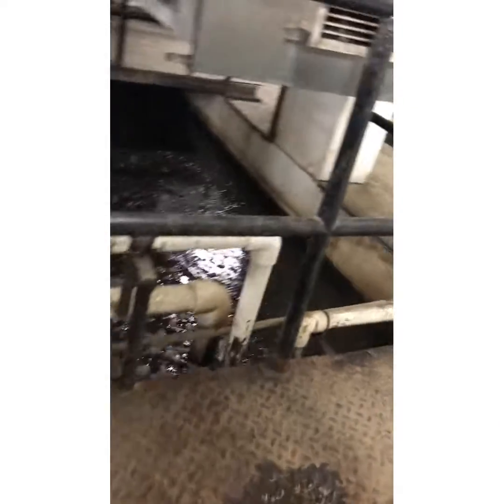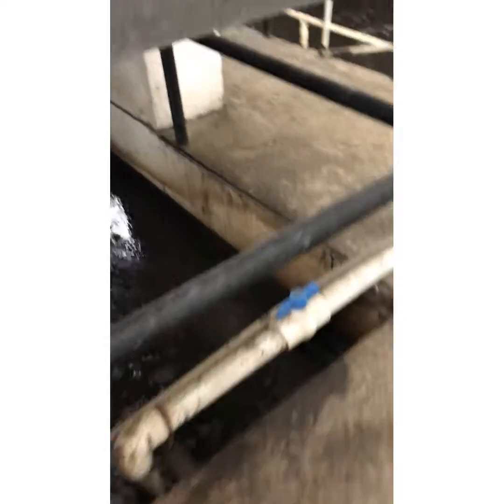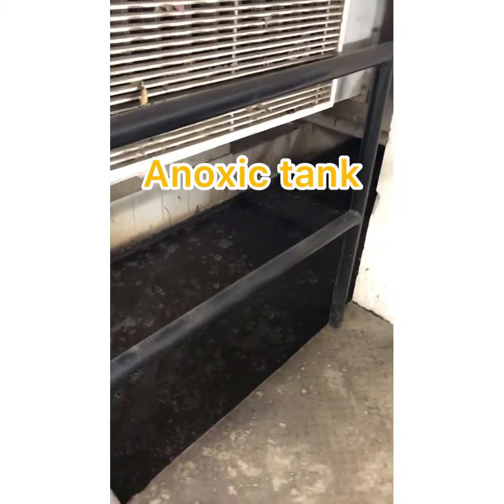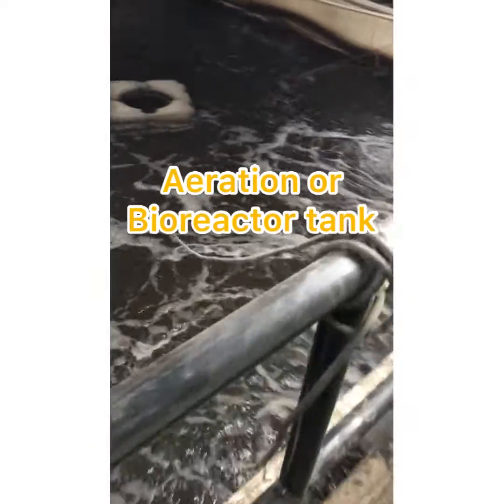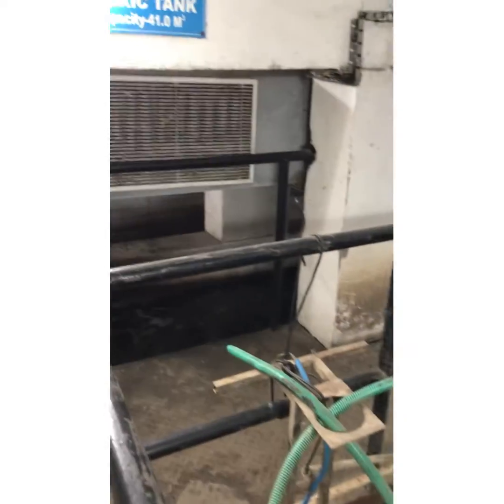Now it goes to another tank, and this tank is the anoxic tank. So this tank is anoxic, where the denitrification process takes place. Here nitrogen is removed, and the next unit is aeration, or we call it the bioreactor tank. This is the heart of the plant, where all the reactions, microorganisms and all take place.